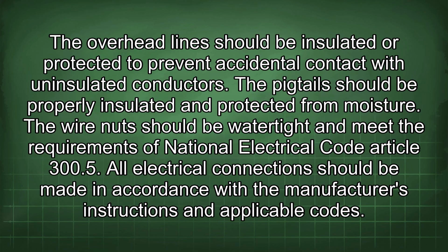The overhead lines should be insulated or protected to prevent accidental contact with uninsulated conductors. The pigtails should be properly insulated and protected from moisture. The wire nut should be watertight and meet the requirements of National Electrical Code Article 300.5. All electrical connections should be made in accordance with the manufacturer's instructions and applicable codes.